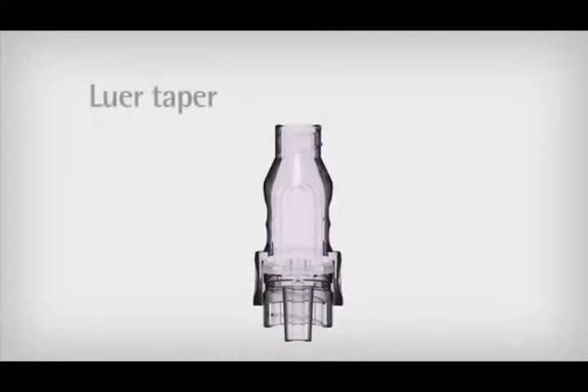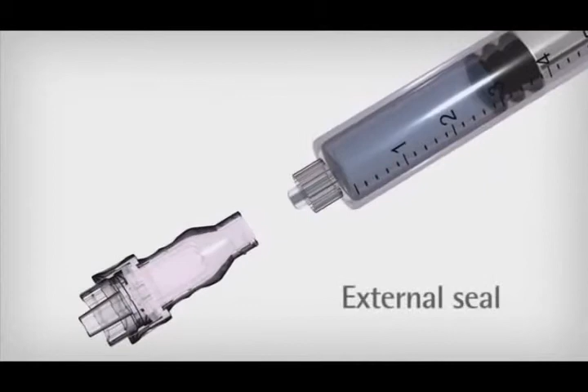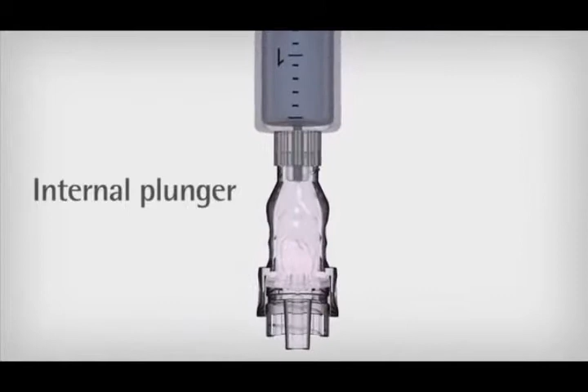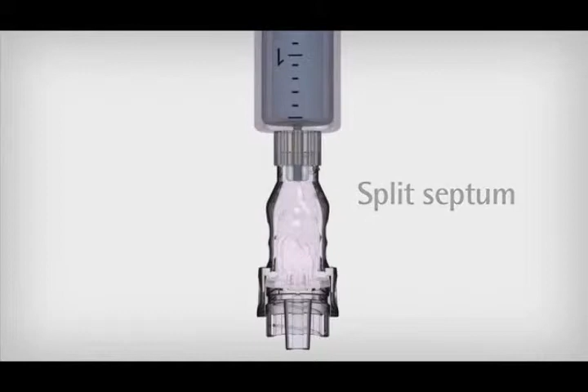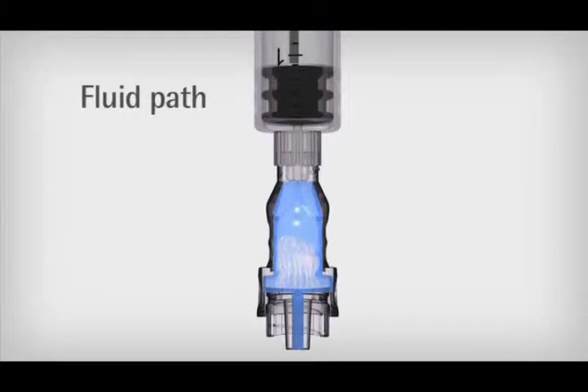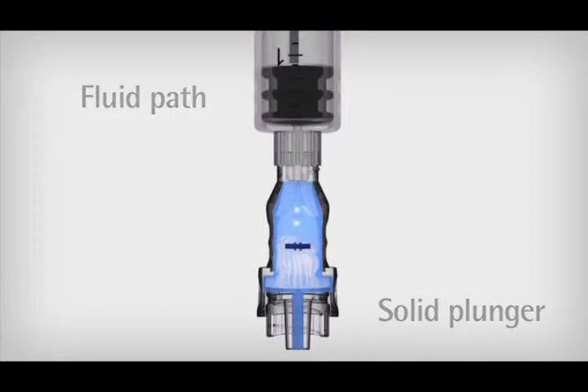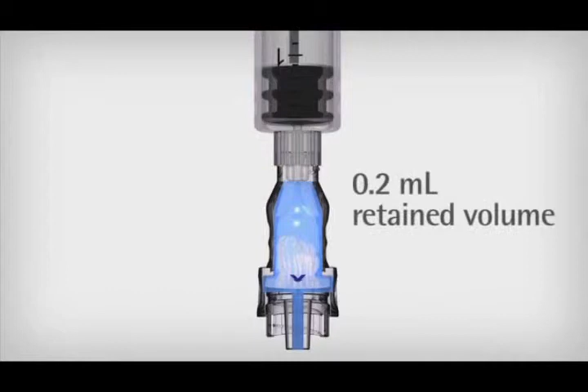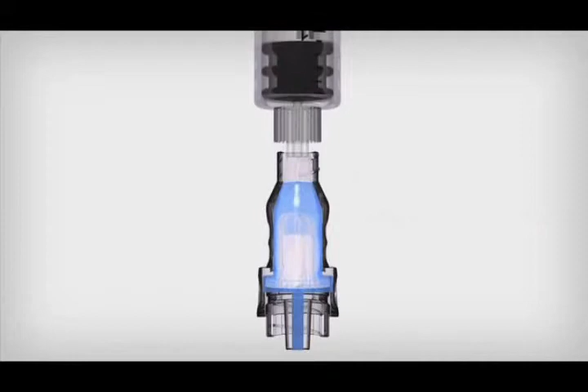A view of the inner components and fluid flow tells an important story. Upon connection with a Luer lock syringe or IV tubing, the external seal of Caresite opens. Then, pressure on the internal plunger opens the flow path, so fluid can flow through the split septum and into the device. This design allows the fluid to flow in an open, unrestricted way all around the solid plunger. There are no interstitial spaces or hidden areas where fluid could accumulate and become trapped. The fluid volume retained by Caresite is a mere 0.2 milliliter. When the syringe or IV tubing is disconnected, Caresite automatically closes.